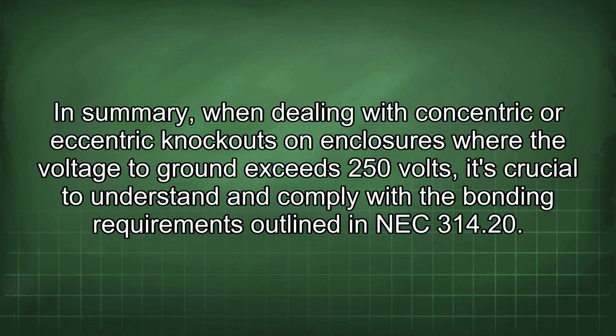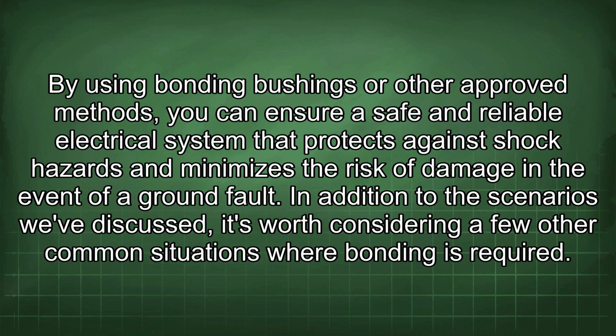In summary, when dealing with concentric or eccentric knockouts on enclosures where the voltage to ground exceeds 250 volts, it's crucial to understand and comply with the bonding requirements outlined in NEC 314.20. By using bonding bushings or other approved methods, you can ensure a safe and reliable electrical system that protects against shock hazards and minimizes the risk of damage in the event of a ground fault. In addition to the scenarios we've discussed, it's worth considering a few other common situations where bonding is required.